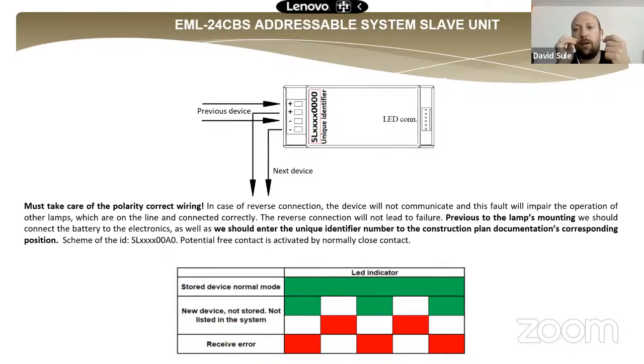We can visually check when we are near the light. We can see the LED indicator, and we can read all of the status information with the end user software or the graphics software. And we can program the fault relays of the panel to send normally closed or normally open contacts to, for example, the BMS or any other system. And we have a Modbus communication directly to the BMS.